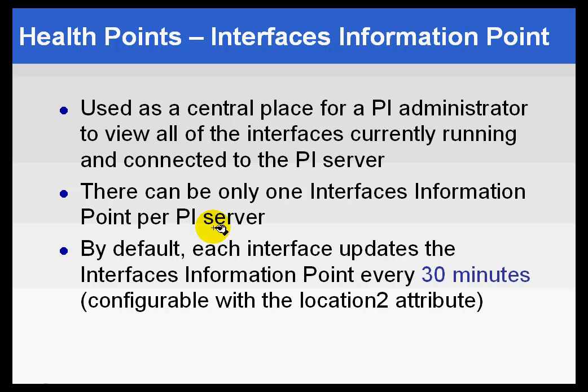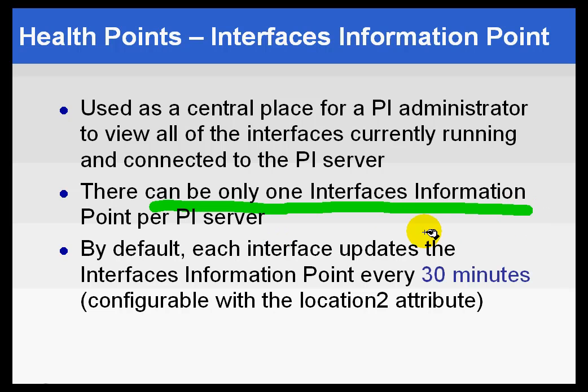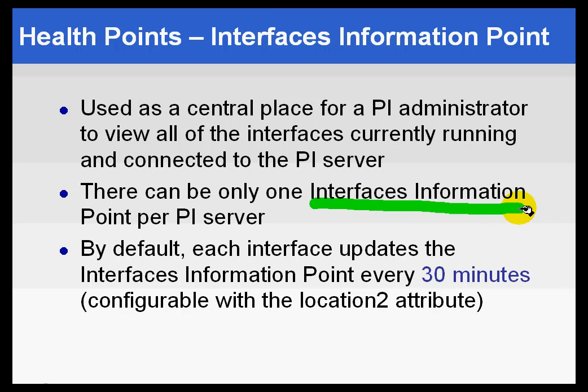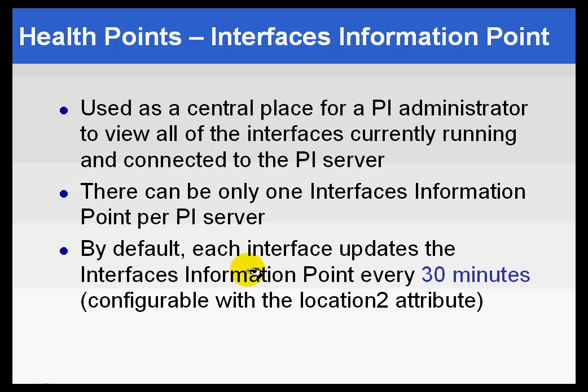So it is a string tag, and there can be only one Interface Information Point. That's the name of it, Interface's Information Point. There can only be one of them per PI Server because all of the different Interfaces are going to be writing to that one point.